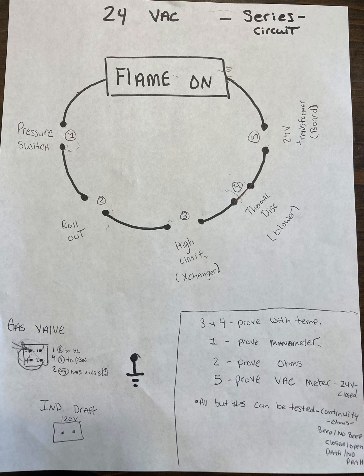How do you prove if that switch is lying or if it's telling the truth? Is it really not meeting those pressures, or is it meeting those pressures and not closing? So, do you really have a problem, or do you have a bad pressure switch? Using a manometer, we can run our tubing in line, and when the induced draft motor turns on, which creates that suction being read by the pressure switch, we can see it right there in digital form, what those real numbers look like. One of two things is going to be happening. You're either not getting the pressures that you need, and that's going to be for a reason. Could be a bird in the flue pipe. There could be an obstruction in there, a jacked up blower. There's a bunch of different things that could be reasons why you're not achieving it.